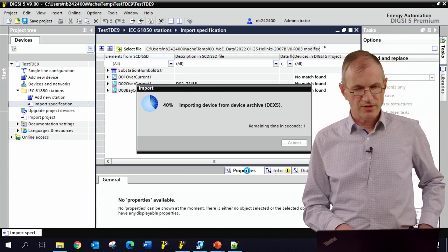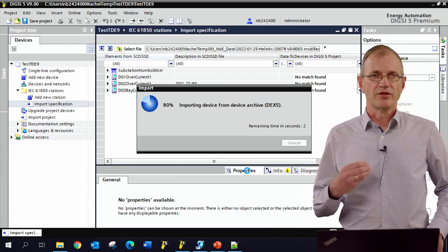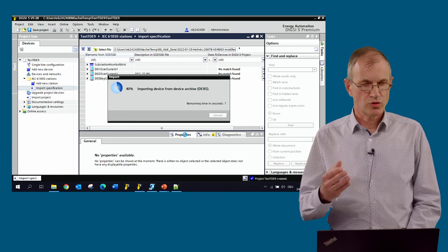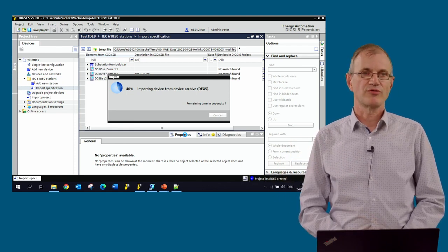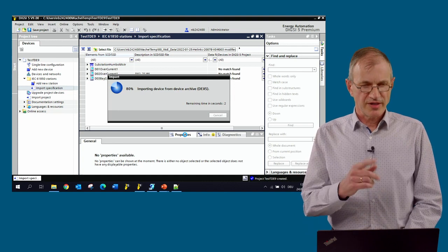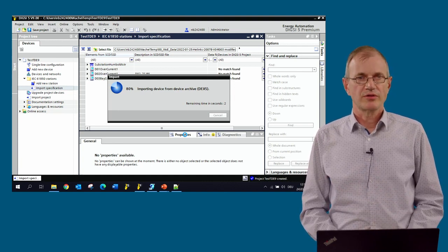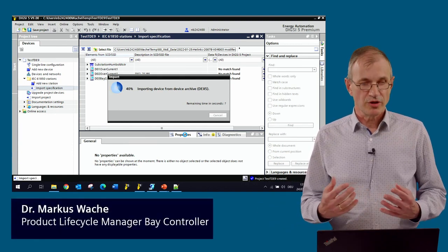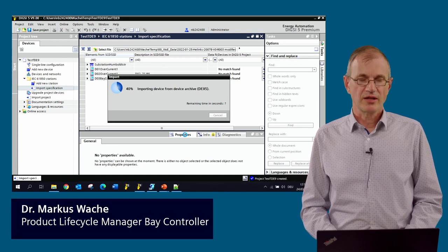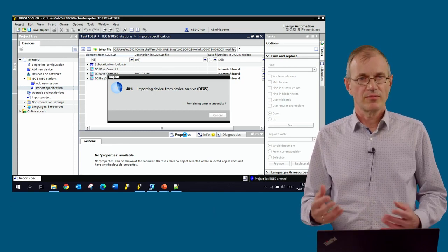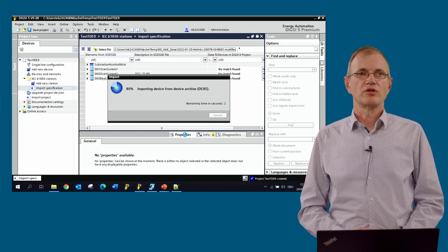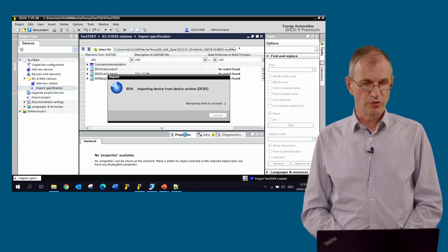It will take 2 minutes or so, and then we can see the difference in the mapping results in this editor if we map the devices to these 2 different IEC 61850 descriptions. What DIGSI does now helps us a lot, because otherwise I would need to instantiate 3 devices from the library, rename them, assign the IP addresses to them, and then maybe switch from one device to another. It's something very useful, which I can only recommend to you for use.